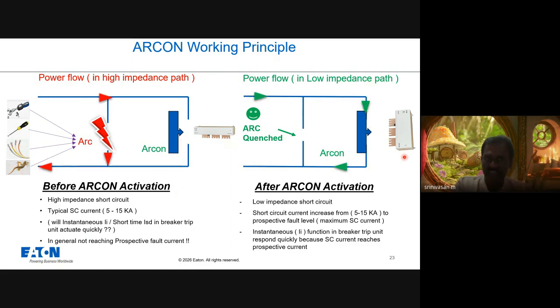Whereas in the other scenario, if you don't have the ARCON in the switchboard and an internal arc happens, for example in the main bus bar system, it may take a number of days, even a week or 10 days. That can be totally avoided. By using the ARCON, you put the switchboard back into service in less than 45 minutes. That is the only thing any facility management team needs to think of.